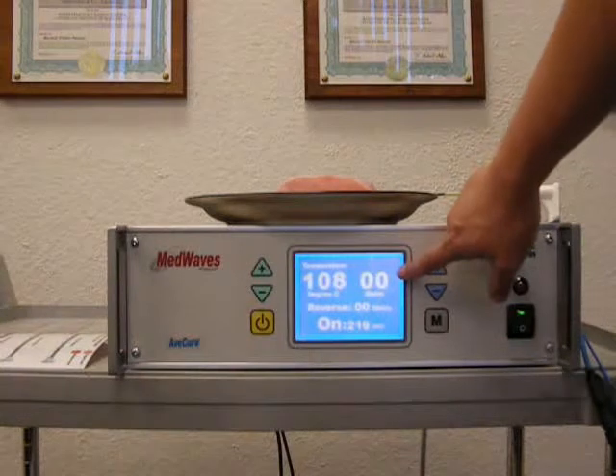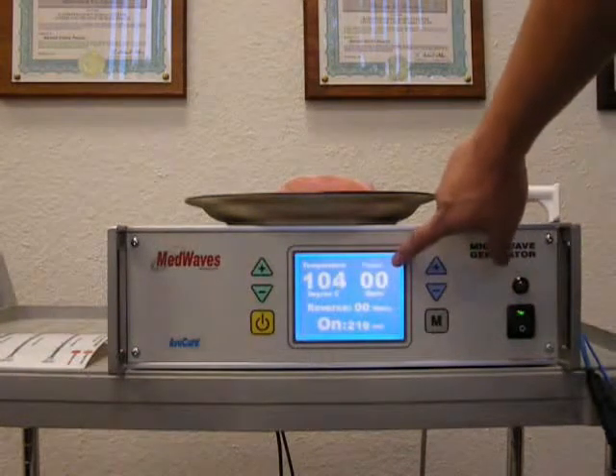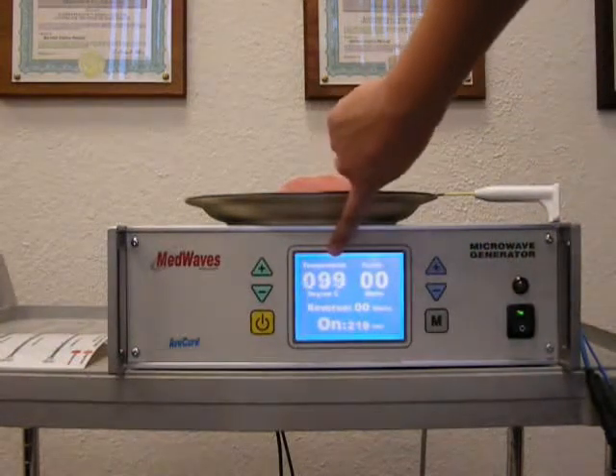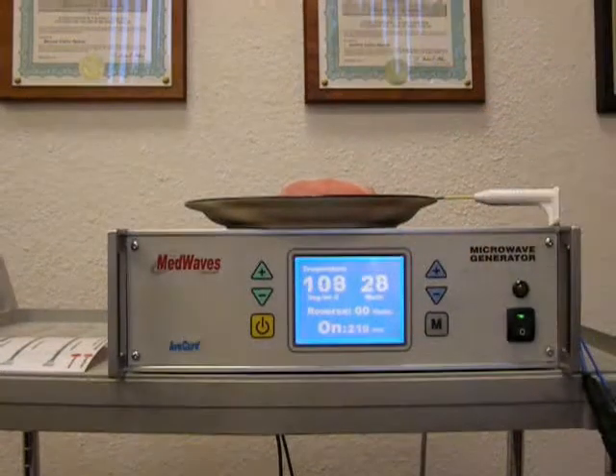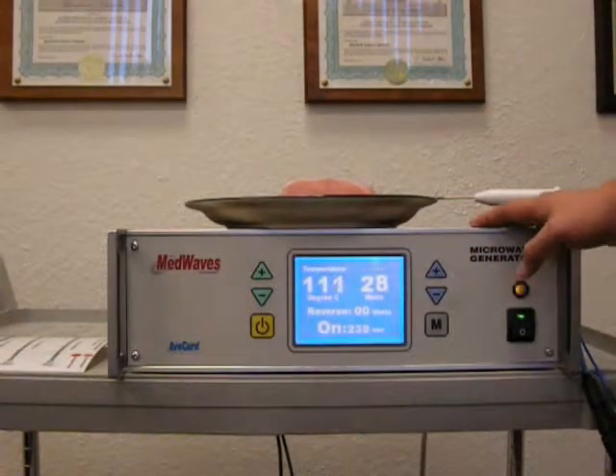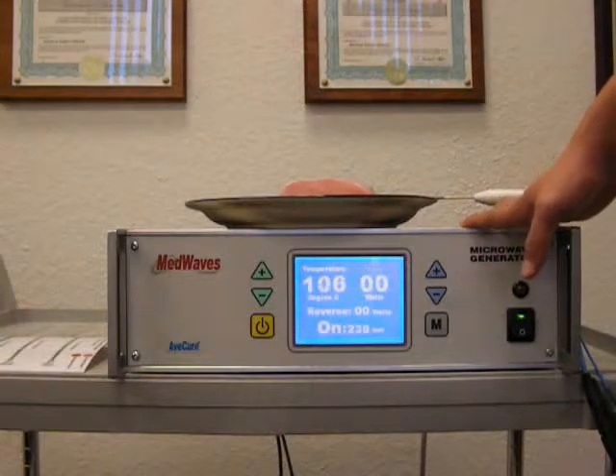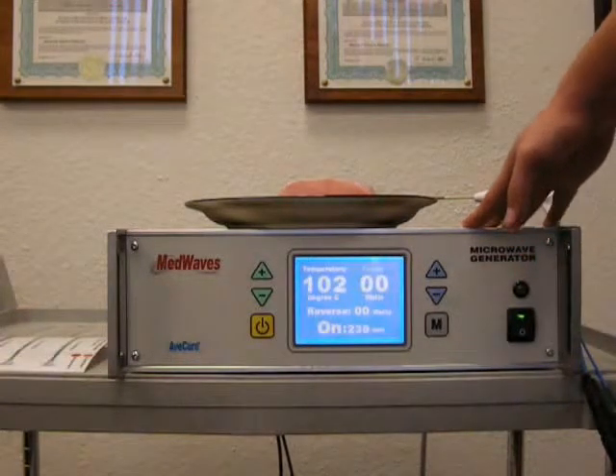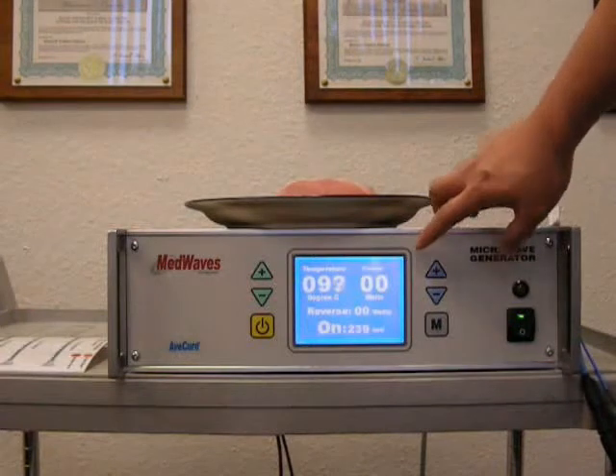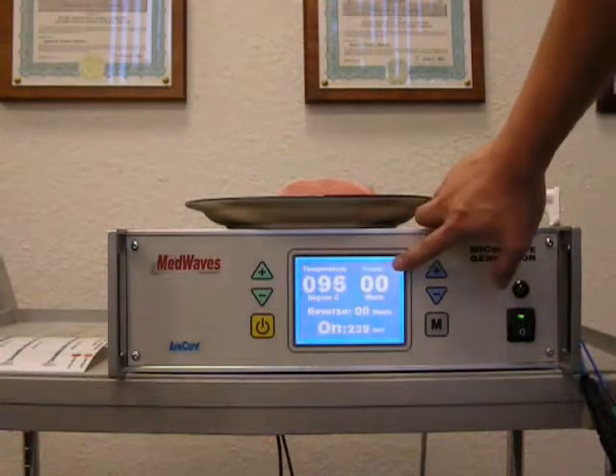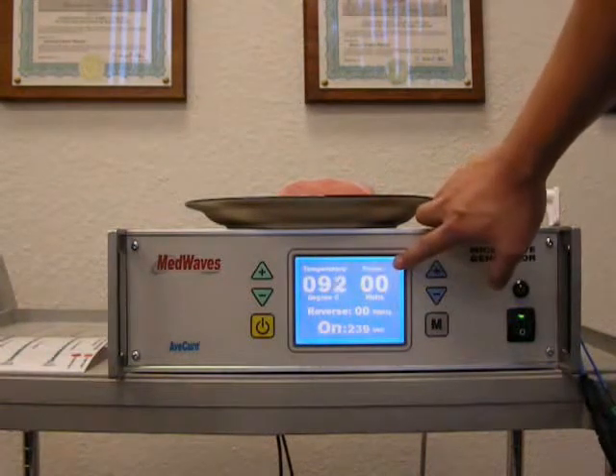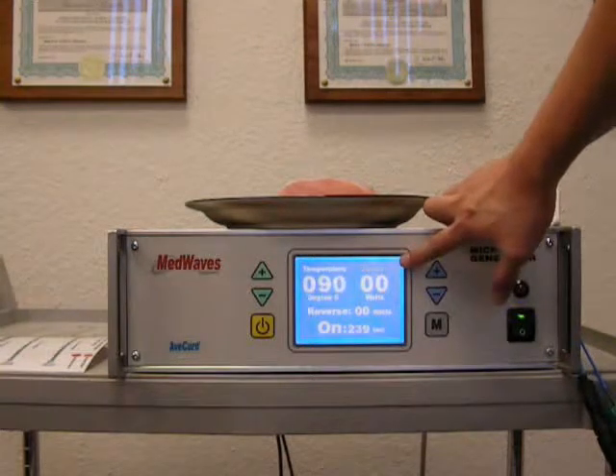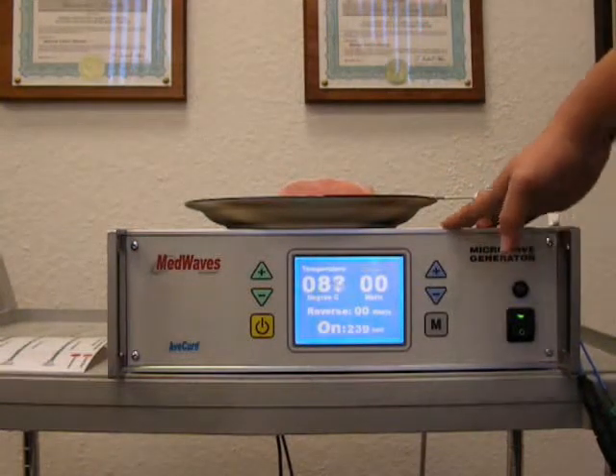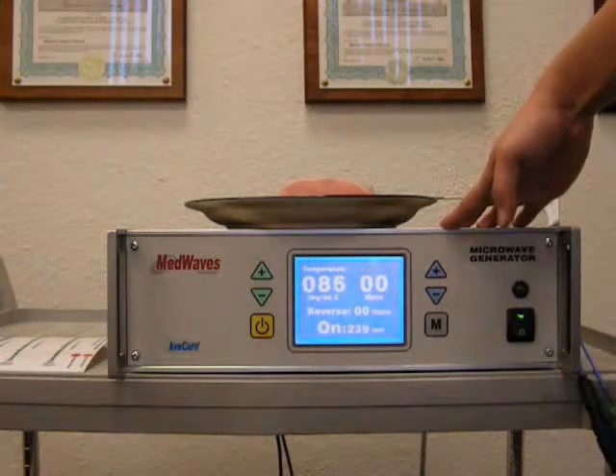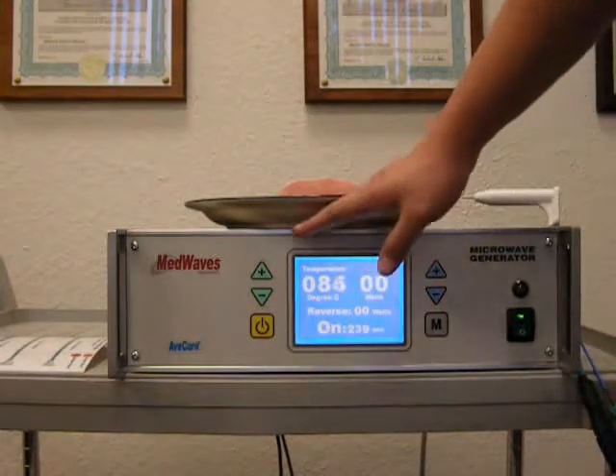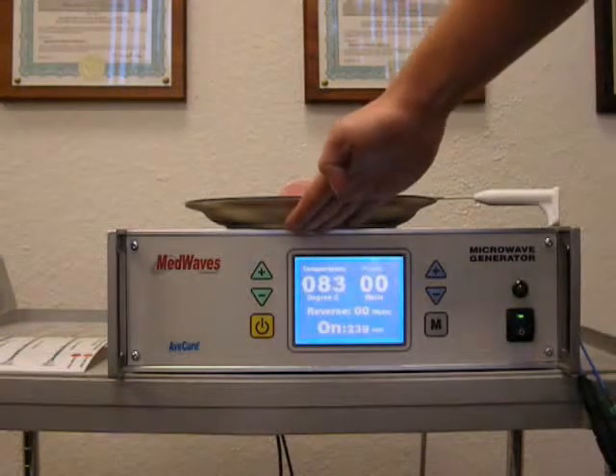See, now it's in power mode because power is flashing. Before, in temperature mode, the temperature was flashing. Again, in temperature control mode, if the power drops below 20 watts, the generator will automatically switch to power control mode. Right now it's in power control mode because the power is flashing. In power control mode, the generator will put out a constant amount of power to regulate the temperature between the set temperature and a 30-degree window.